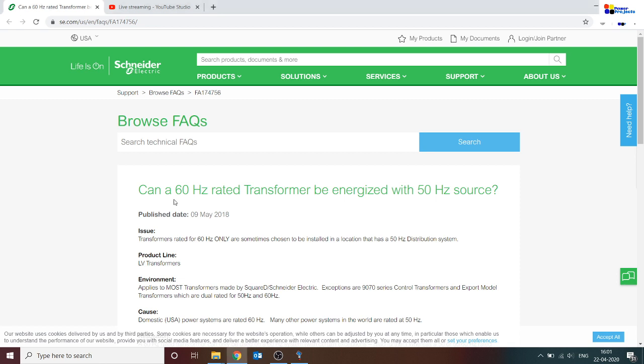We know the equation which defines the voltage induced in the transformer, relating the voltage with respect to the flux, frequency, form factor, etc. If you write the voltage equation E or V in a transformer, it is 4.44 F phi T. You may be aware of that equation, and you also know why V by F has to be maintained in all electrical equipment, and why you have a V by F relay or overfluxing relay in transformers.